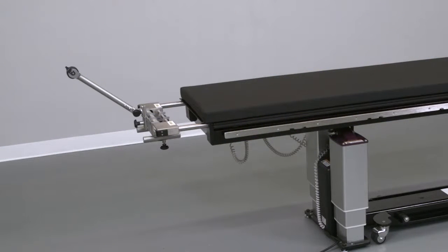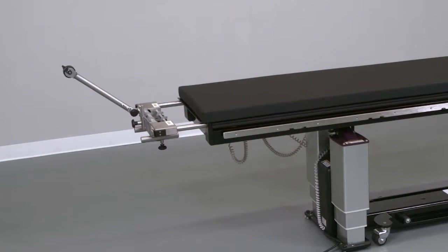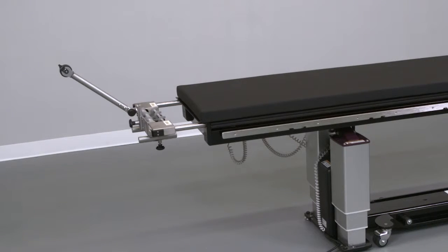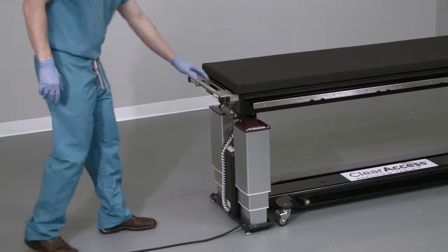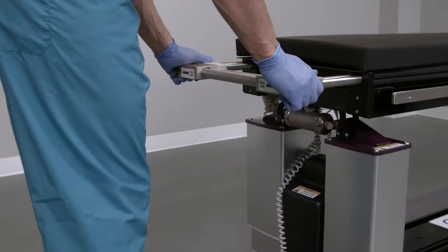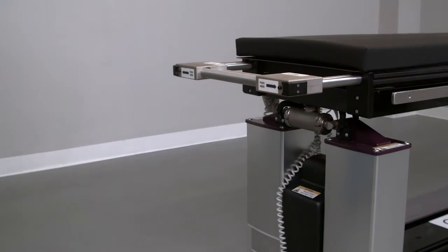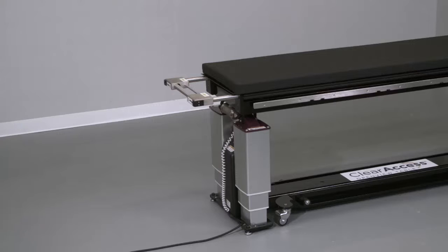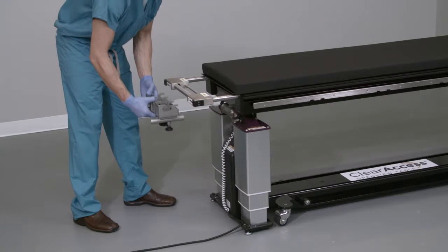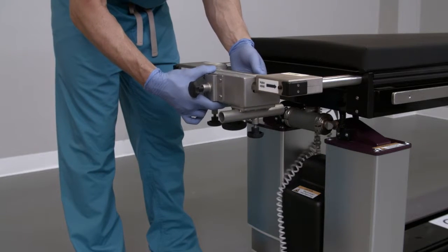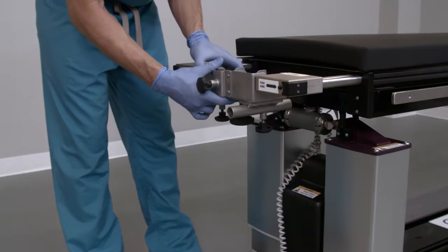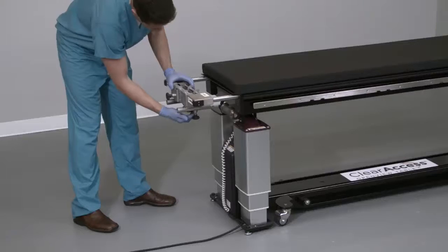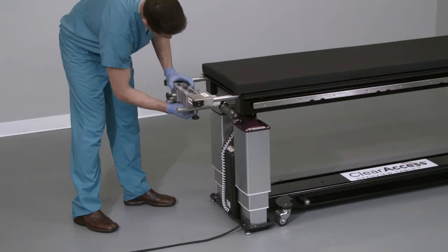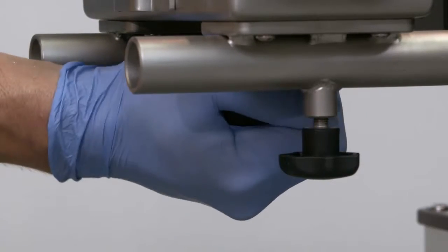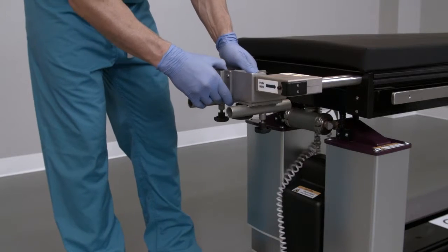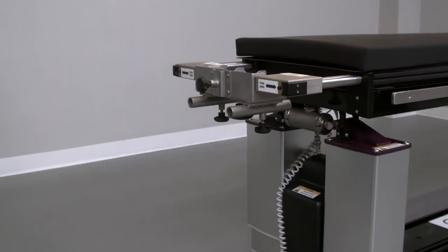To conduct ACDF procedures utilizing rope traction, it'll be necessary to install the cranial stabilization adapter and rope traction device. Begin by grasping the handle at the head end and pulling outward until it clicks in place. Verify that it's locked in the extended position by pushing inward. Next, install the cranial stabilization adapter by bringing the adapter underneath and lifting upward to engage both the handle and the stabilization bar in the appropriate grooves of the cranial stabilization adapter. Lock the adapter onto the handle by firmly hand-tightening the large locking knob on the bottom of the adapter. Verify that the system is firmly locked by pulling on the components to ensure no movement.